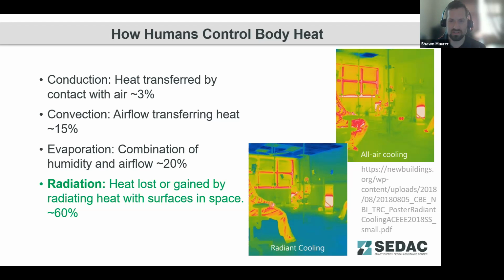So what we're showing on the screen here, the top left image is air cooling. So we're maintaining lower temperatures for that discharge air. We've got increased energy consumption to do so, to deliver that cooler air into the space. But the surfaces in that space are kind of a median temperature. And so particularly next to the windows there, you can see a higher temperature. An occupant sitting there is going to feel much warmer than the person sitting closer to the camera there in the bottom right corner of that image.